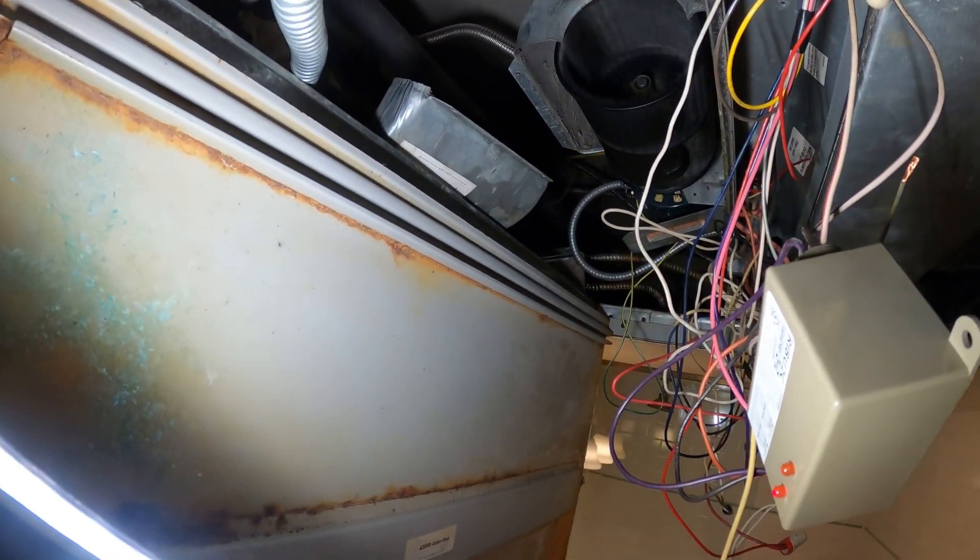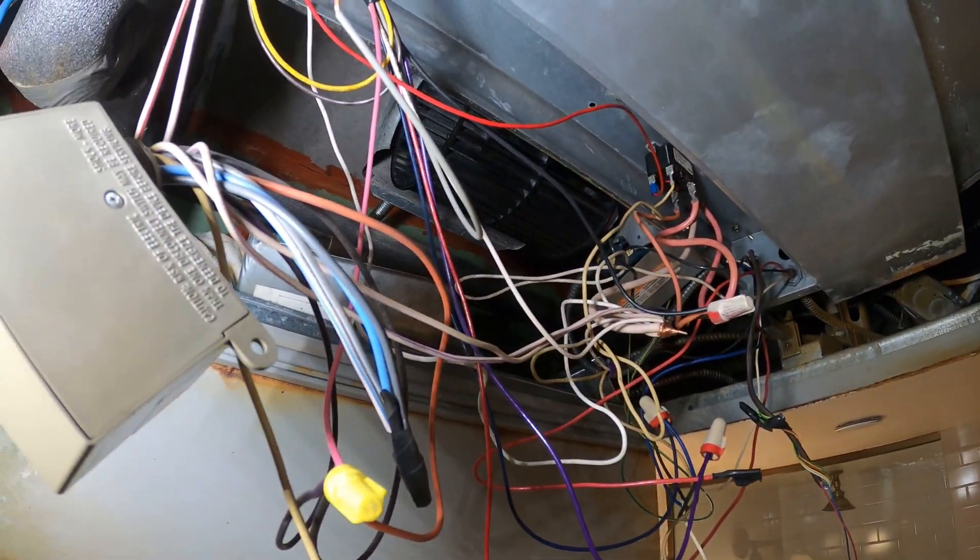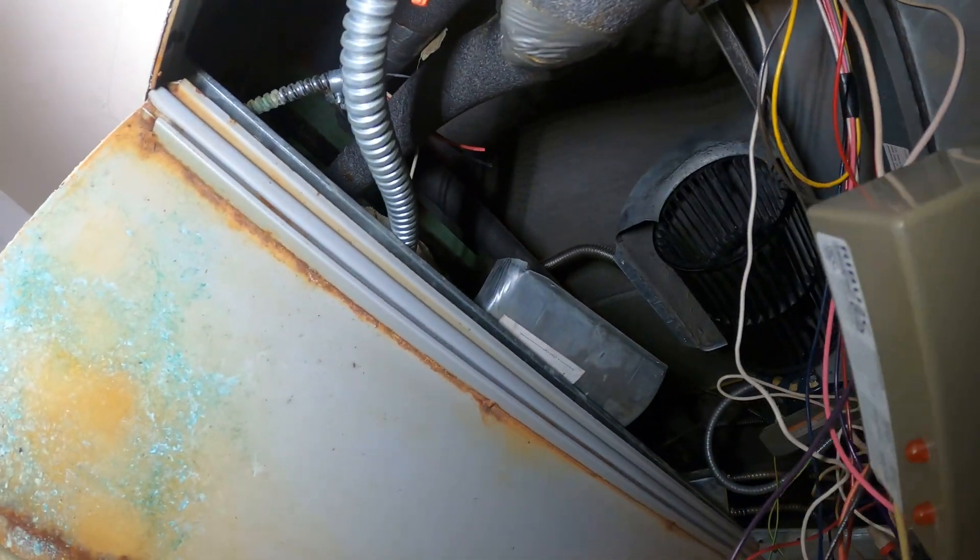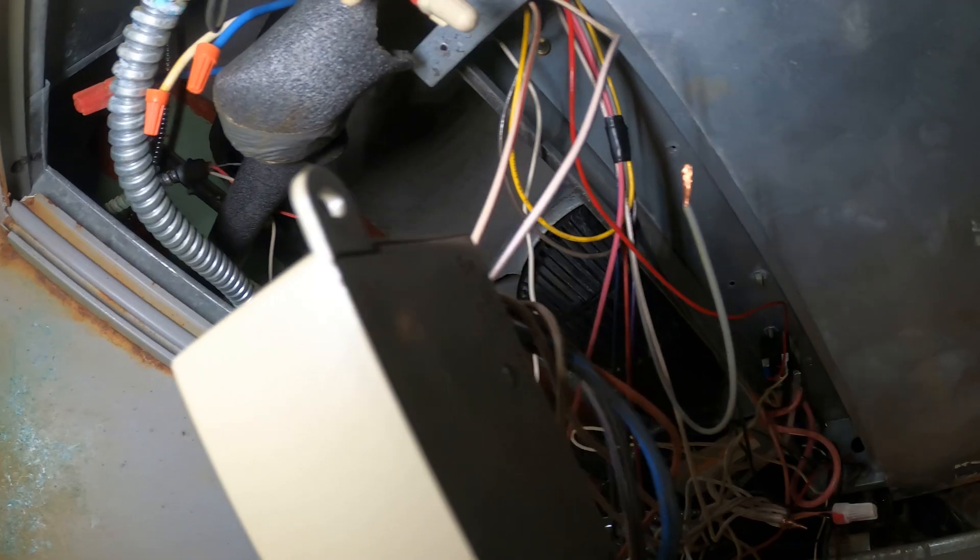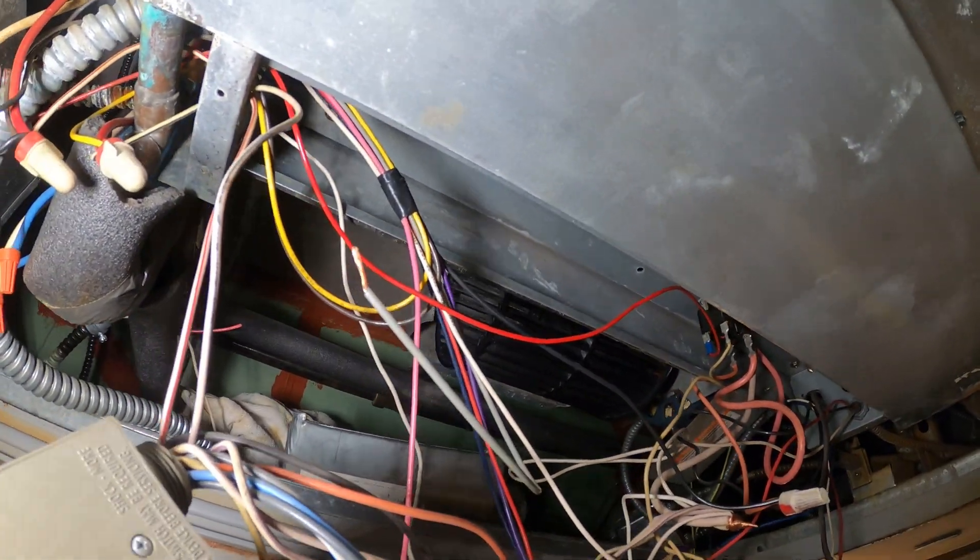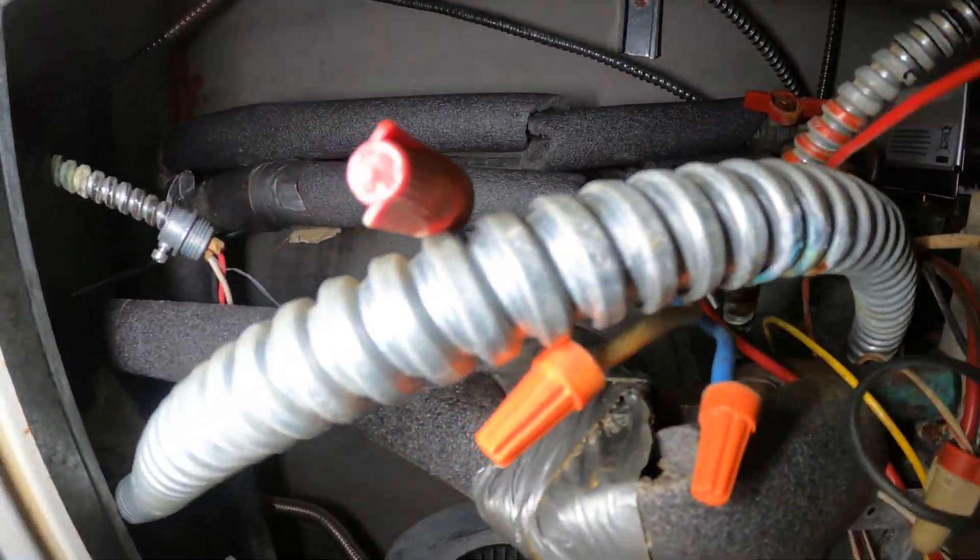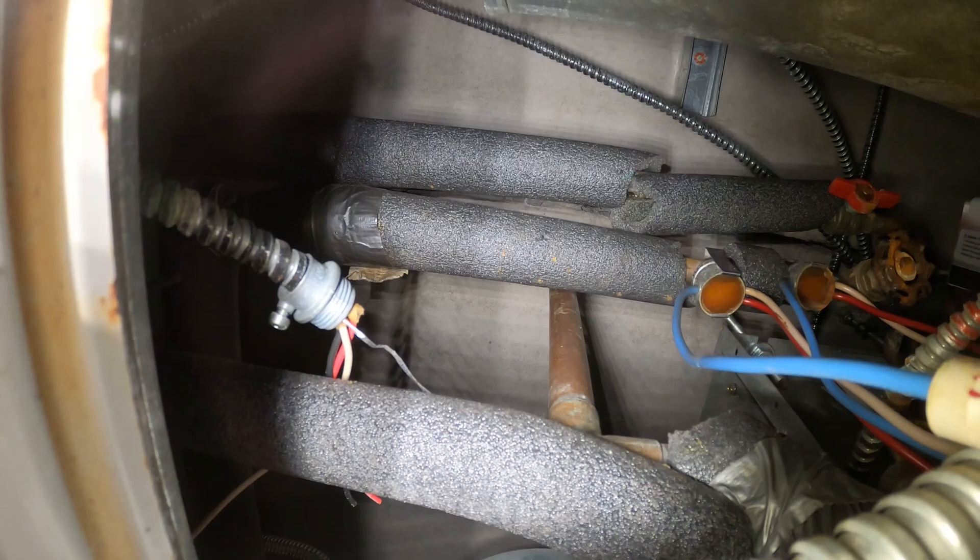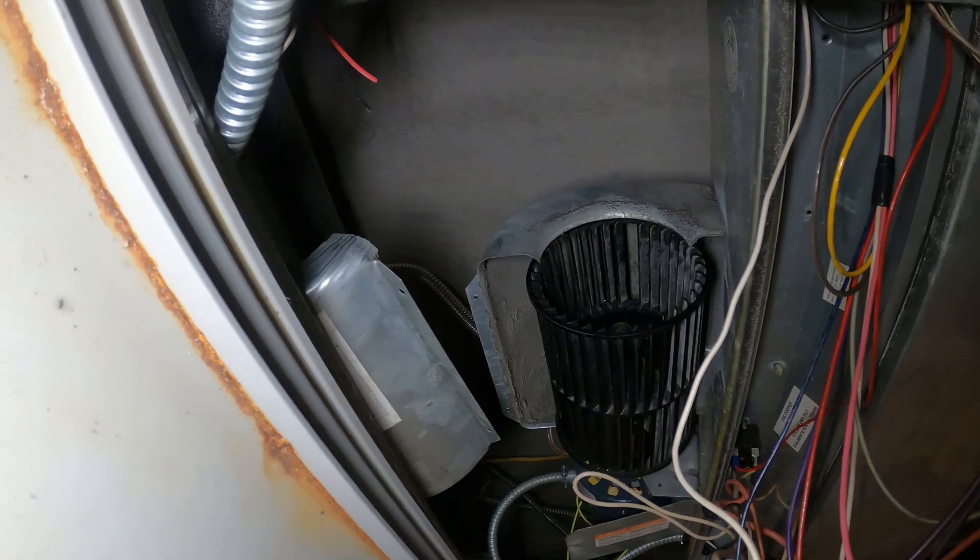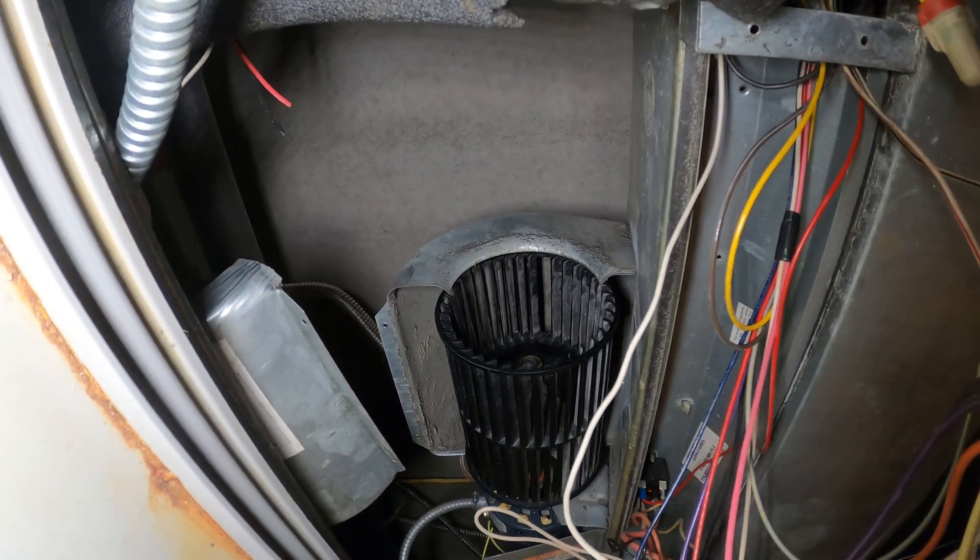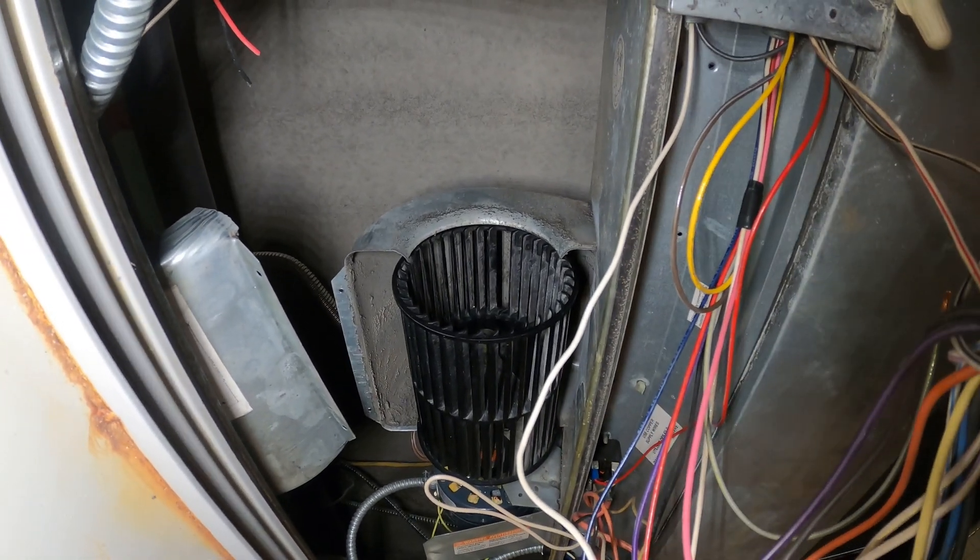Where is our cooling? Cooling. Alright, so we got three fan speeds and display. But, we are now in cooling season. We have no cooling. So, I need to look into the wiring here from the thermostat. Figure out who's who. I noticed that brown wire. We also have, if you look up top, connected to those blue wires. The blue, white, and red. Those are two pipe sensors. So, depending on the temperature of the pipe, you'll know if you should energize the emergency electric heat.